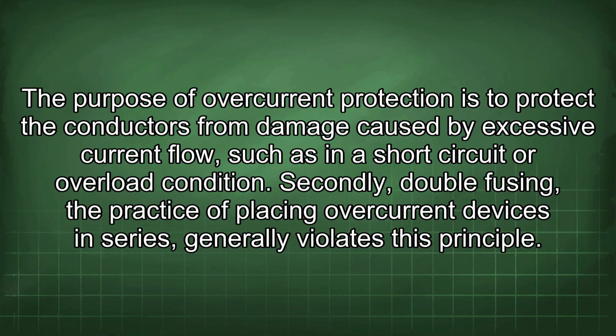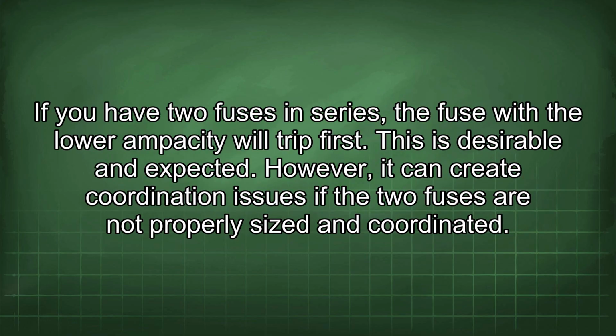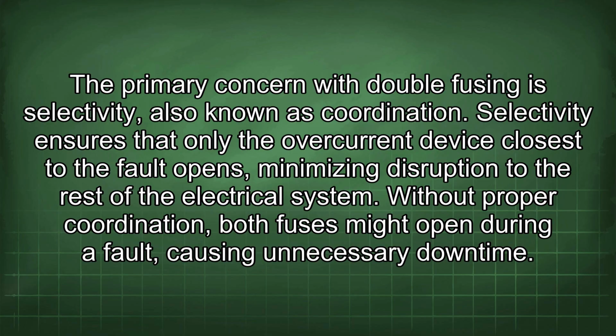Secondly, double fusing, the practice of placing overcurrent devices in series, generally violates this principle. If you have two fuses in series, the fuse with a lower ampacity will trip first. This is desirable and expected. However, it can create coordination issues if the two fuses are not properly sized and coordinated. The primary concern with double fusing is selectivity, also known as coordination. Selectivity ensures that only the overcurrent device closest to the fault opens, minimizing disruption to the rest of the electrical system. Without proper coordination, both fuses might open during a fault, causing unnecessary downtime.